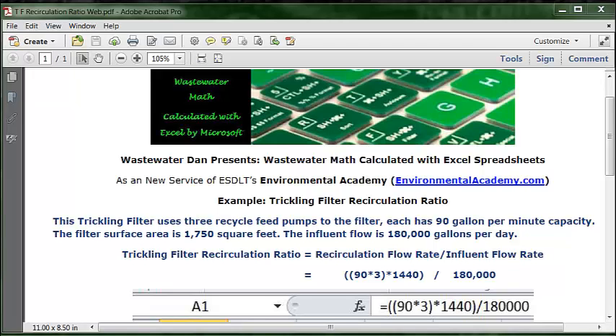In calculating the recirculation ratio, this trickling filter uses three recycle feed pumps. Each recycle feed pump has a 90 gallon per minute pump capacity. The surface area of this trickling filter is 1,750 square feet (FT²). The influent flow is 180,000 gallons per day.